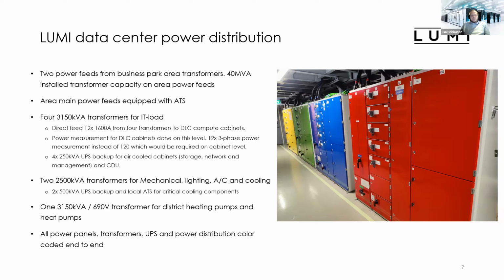And power measurement on the direct liquid cooled cabinets is done on that level. So instead of installing a power measurement system for every single power feed of the LUMI direct liquid cooled cabinets, we only have 12 three-phase power measurements installed instead of having over 120. Basically, this cabinet level measurement is only needed for the HPC runs, so we can combine our IT total power consumption on this higher level.